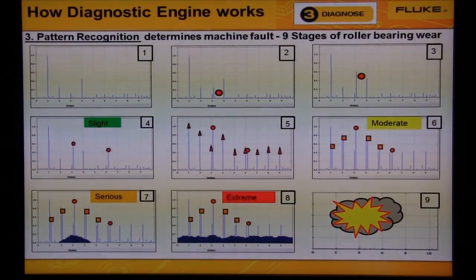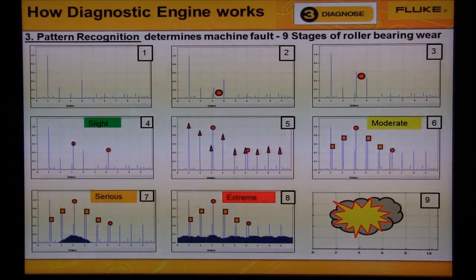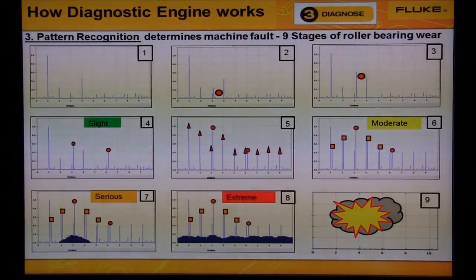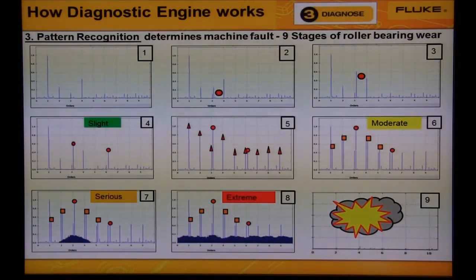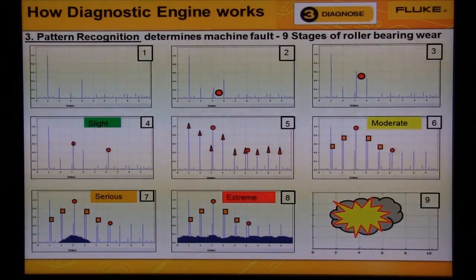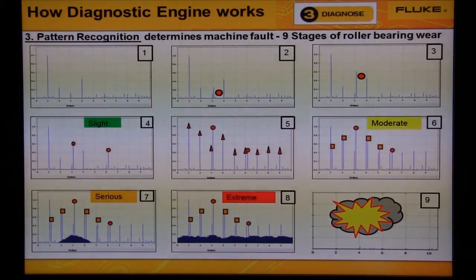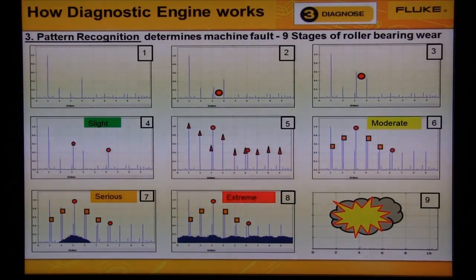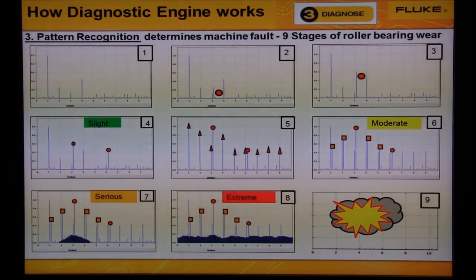In step number three, we compare the exceedances of the baseline to 4,700 rules. Of these 4,700 rules, there are four common faults that we see every day: imbalance, misalignment, looseness, and roller bearings. We'll focus on these four faults in the 810.